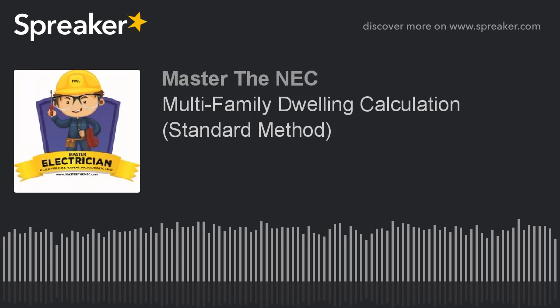Now, in this case, you're coming down to the number of appliances. There's 18 of them. Then you go all the way over to the right, and it results in 33 kW. So that is the value you're going to have. That's 33,000 VA. Now, just like we did before in 220.61(B)(1), you're going to be able to apply 70% to this value for your neutral load.